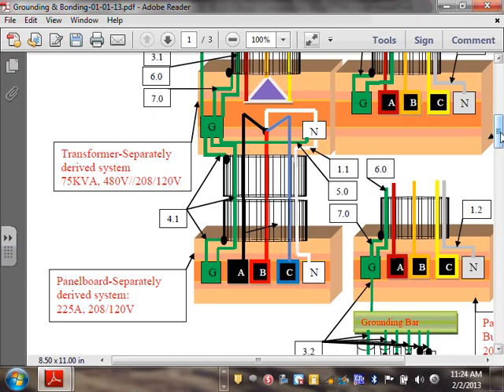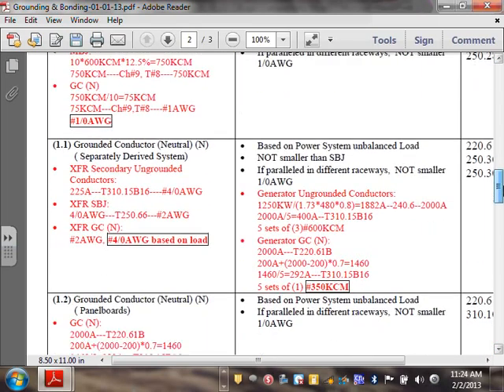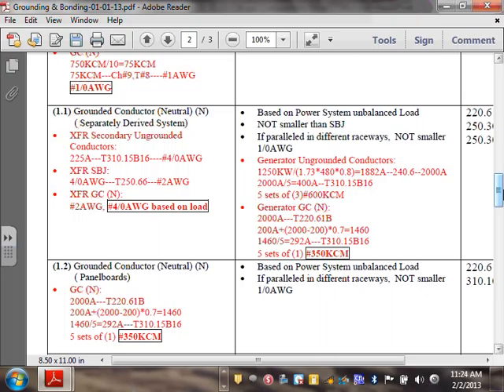That's the white conductor. How do you size that conductor? A lot of us guys, in a 225 amp panel, what do we do? Full neutral, which is a very good idea. Why? Because you're dealing with lighting and receptacle panels, harmonics, full neutral. But what's your minimum though? Here's what your minimum is. So if you go to 250.30(A)(1) here, can you guys see that?